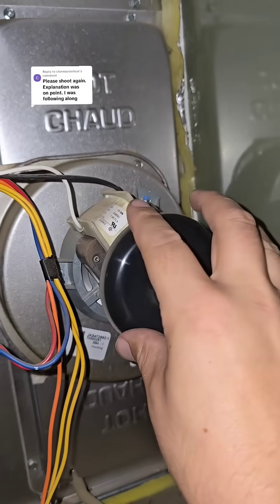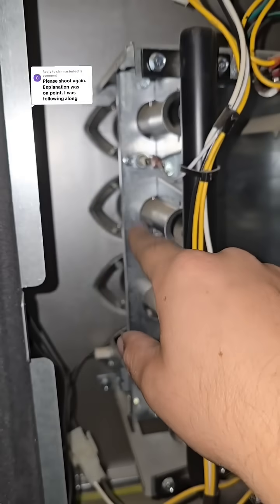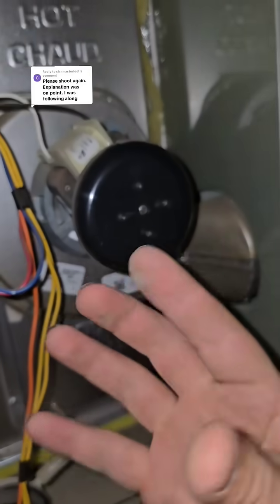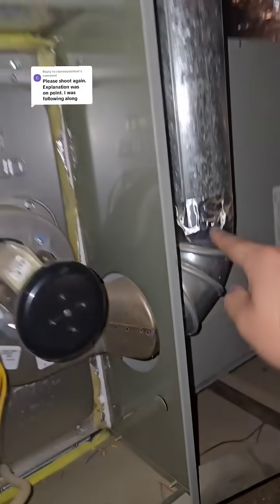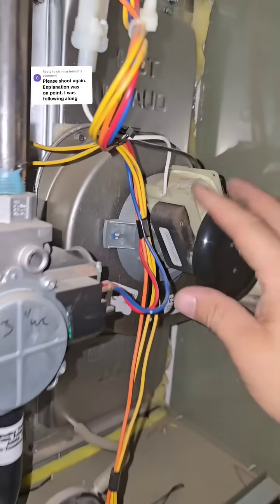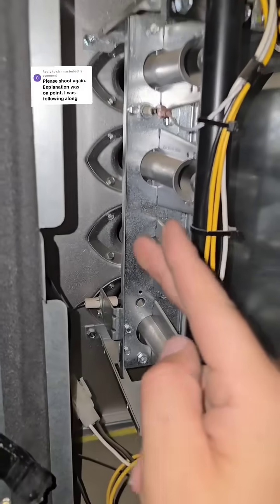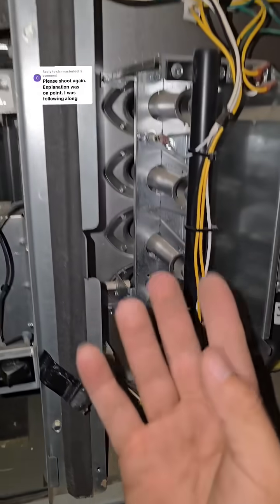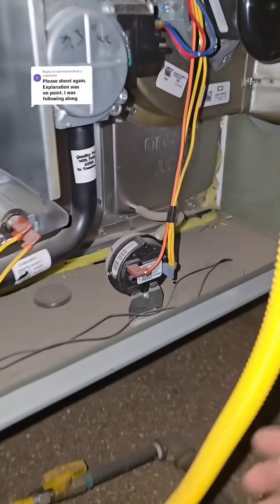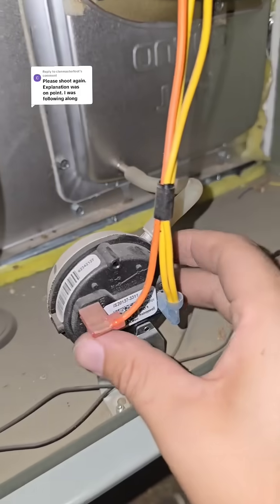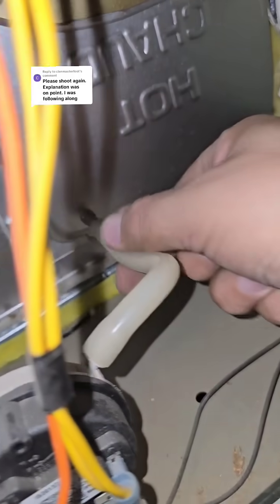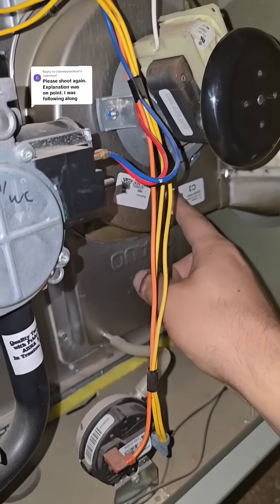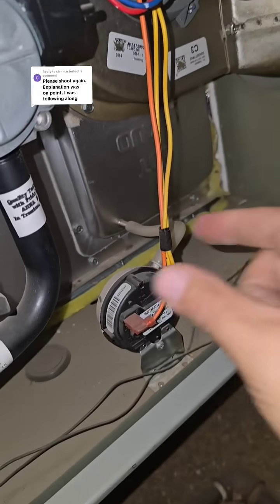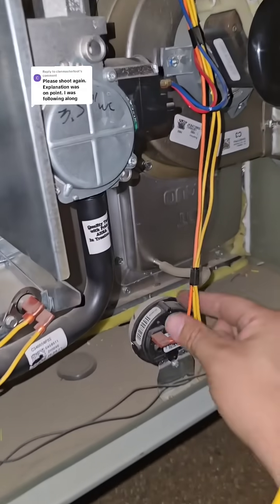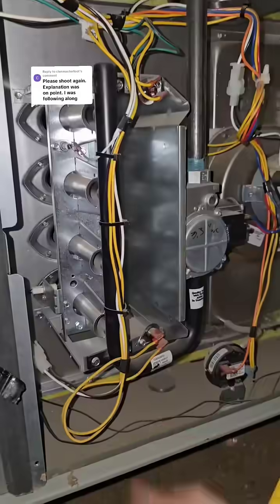Once this inducer motor spins, it's going to be pulling the flames in the burners into the heat exchanger, the firebox. And it will remove the exhaust out the roof. This inducer motor has to be spinning, or the flames won't go in the heat exchanger. They'll just be boiling out, burning the house down. But that's why we got this safety switch right here. It's a pressure switch. This hose right here is connected to the housing of this inducer motor. This hose will pull a negative pressure closing these two wires. These two wires are connected to all your safeties, your rollout switches, your high limit switch, all of them.